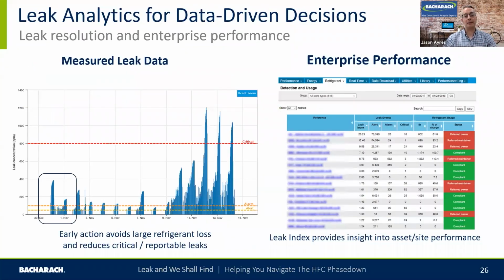And that's where data analytics come in. The Parasense platform that's been designed and developed by Bacharach allows enterprises to manage their refrigerant leak detection alarm information much better. They can see holistically what's going on: which is my worst site for alarms, which is my most problematic site for alarms? Where do I need to target and utilize my maintenance resources to reduce refrigerant usage? And where should I focus? Should I be focusing on the high critical alarms, which are very rare? Or should I be focusing more now on the early action, this low level range, the alert and the alarm area, this under 100 ppm?